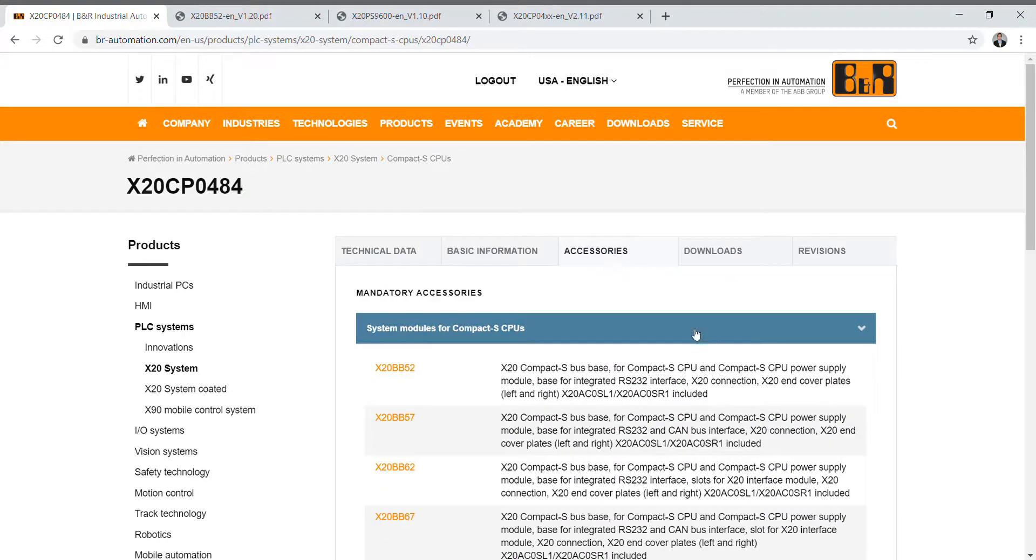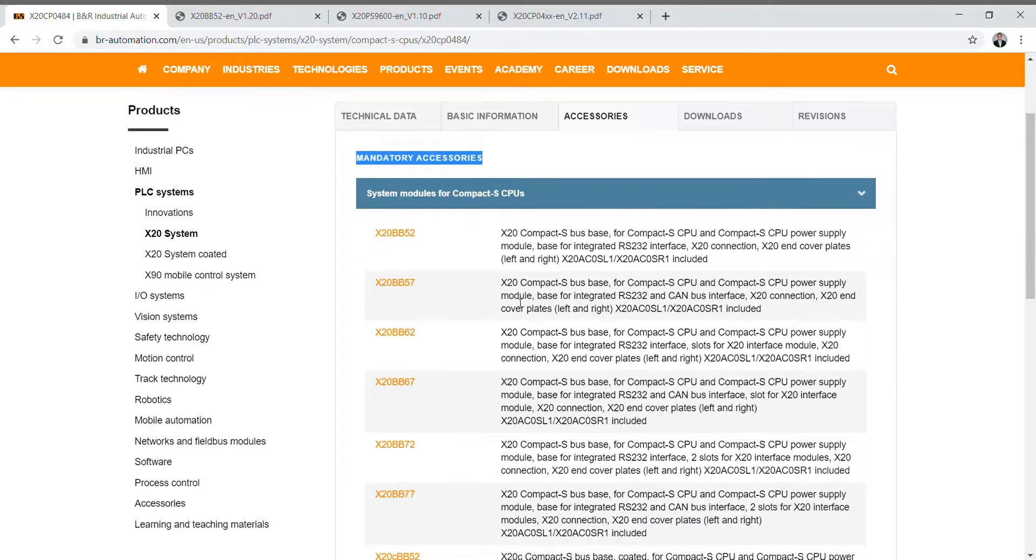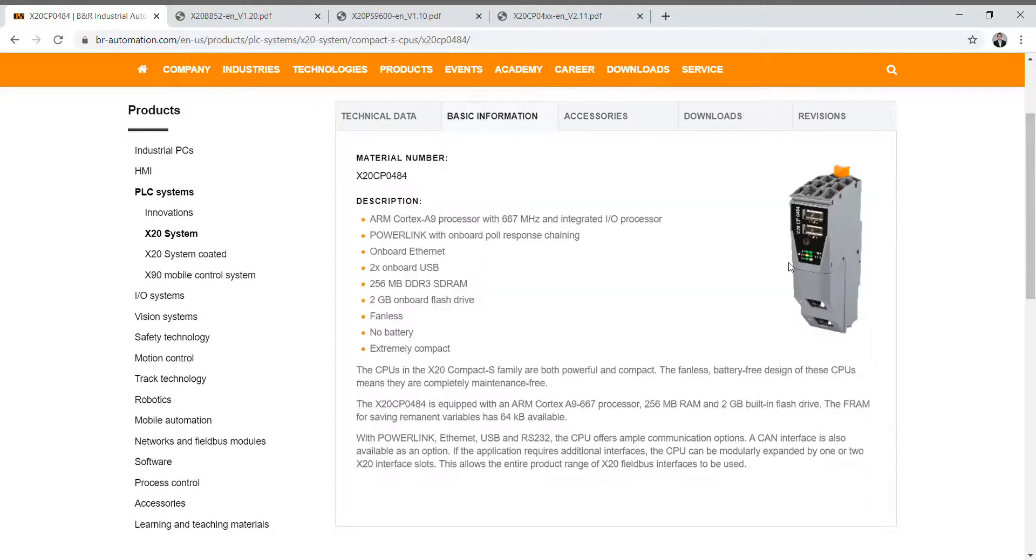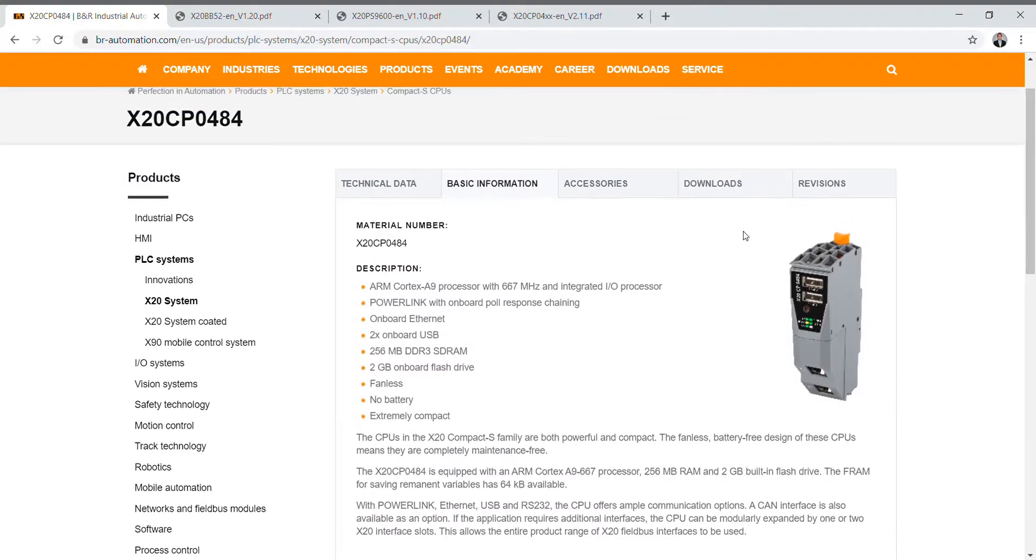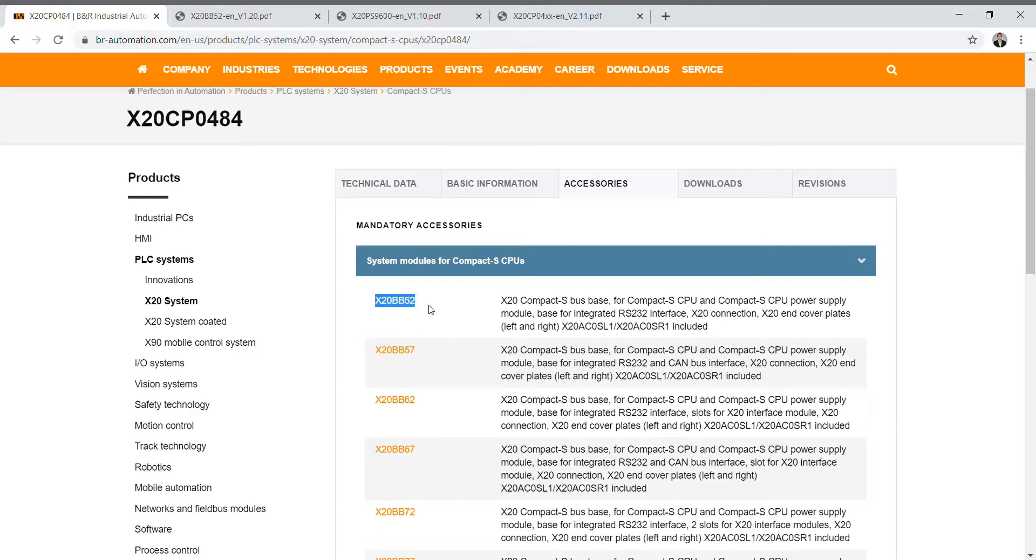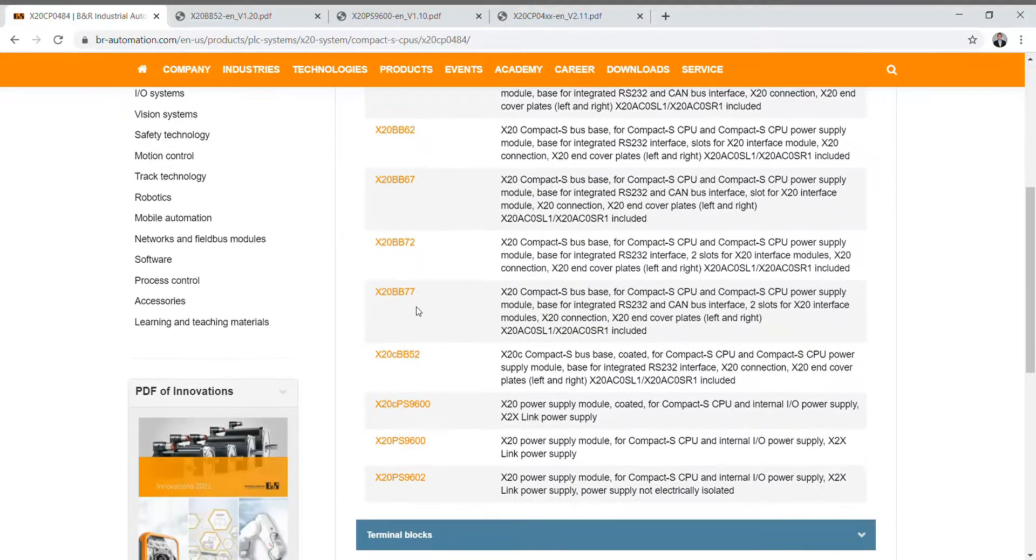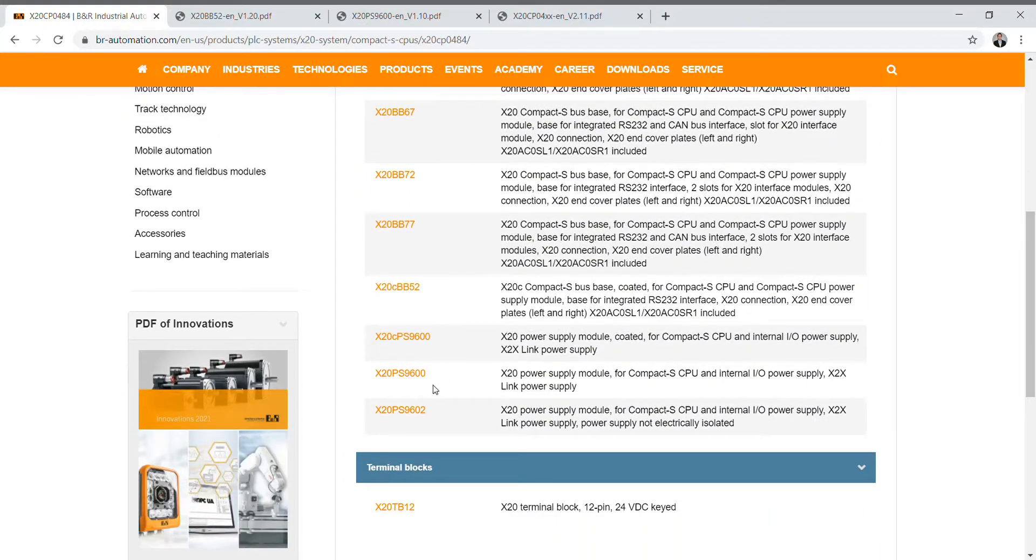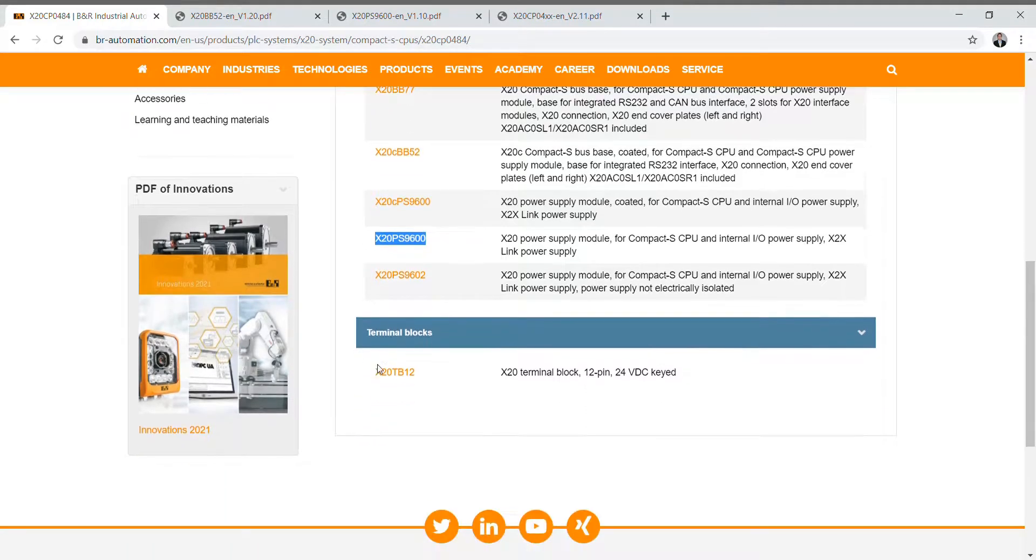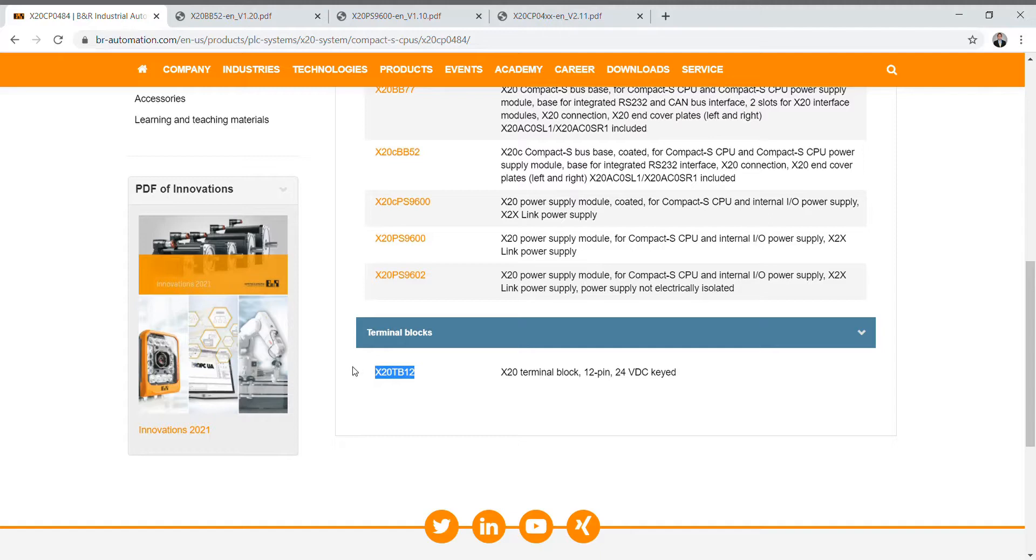If we go to accessories you'll notice there's something that says mandatory accessories. You can't just buy this product by itself and run it like this. You need to have some mandatory accessories. The first one is a bus base or a bus module. The one that I've selected is the X20BB52. The next item that you would need is a power supply module. The one that I have used is the X20PS9600. Last but not least you'll need a terminal block to wire into. That's the X20TB12.